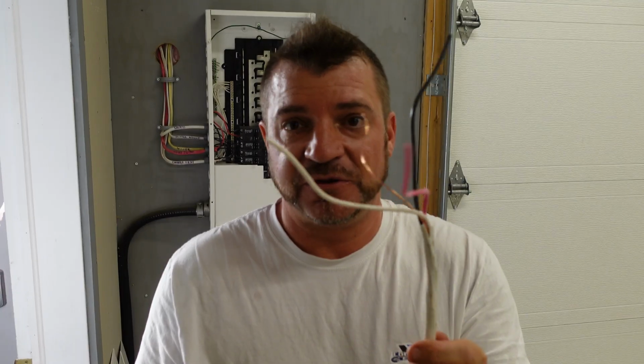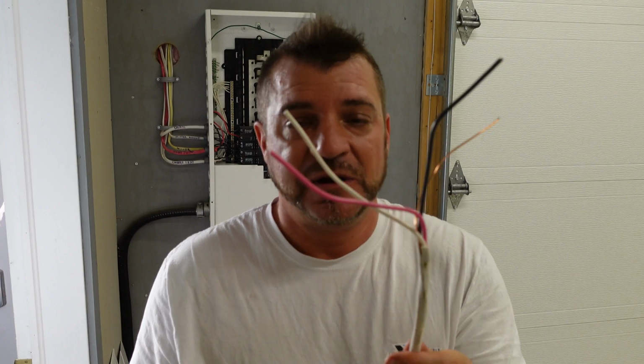So because the 14 gauge wire doesn't have arc fault protection, or the 12 gauge wire doesn't have arc fault protection, we're not permitted to run 3 wire circuits, which sucks, because then it's 2 runs of 2 wire instead of 1 run of 3 wire, which costs more money to wire a home. But of course, that's the whole name of the game. That's why these code update changes come, to keep the system flowing and to make things safer.